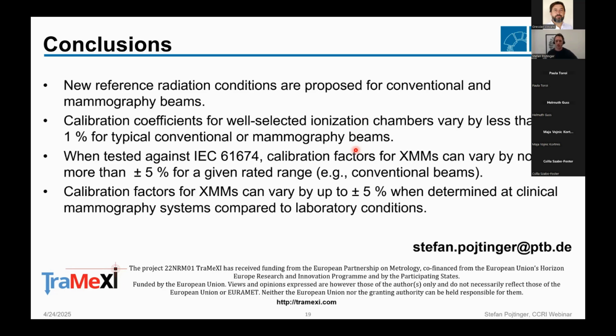For example, RQR for conventional beams. I also showed calibration factors for XMMs. If you determine these at clinical beams and compare that to calibration factors that you determined at laboratory conditions, they can differ by up to 5%. And that's also something to consider. And this is my last slide. And therefore I say thanks for listening, and back to Paula.